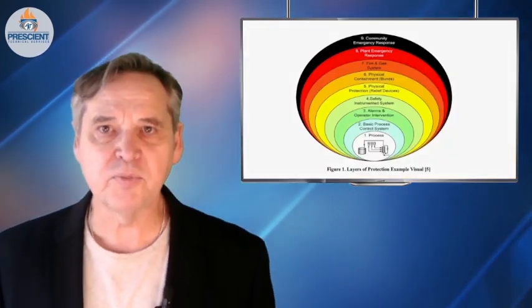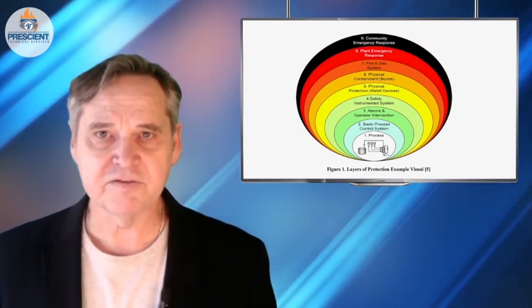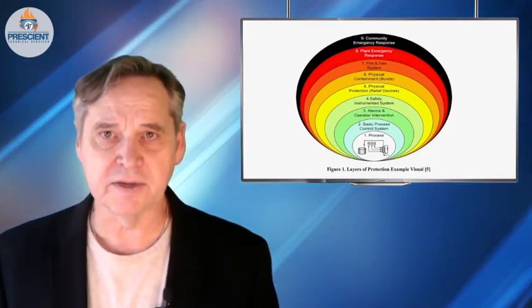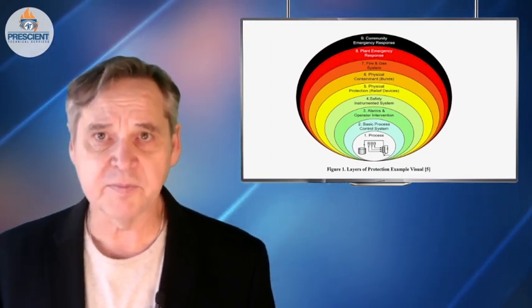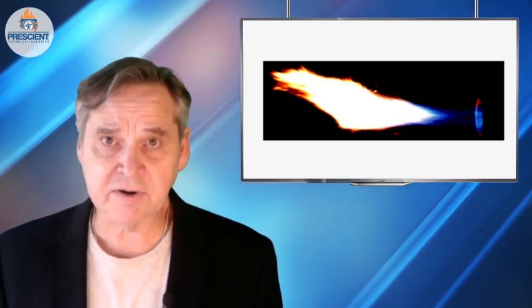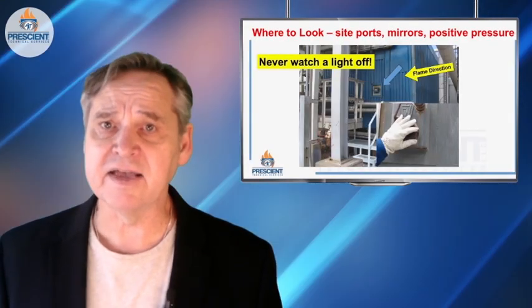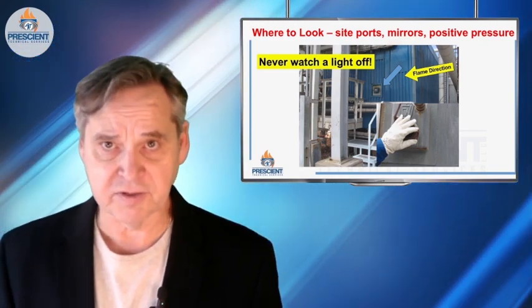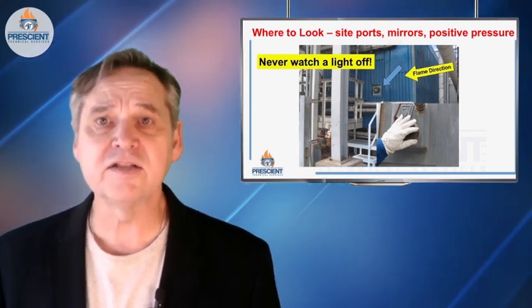How do you mitigate these risks? You do intense quality control management of the water treatment system. Some facilities use third parties to review the water treatment occurring, or build in significant redundancy. I'm also providing in the comments section a PDF of a paper on doing LOPA — layer of protection analysis — on water treatment systems for boilers. Don't forget that burners not set up properly with flames impinging on tubes can also cause premature tube failure. You need a daily flame observation program with people trained to recognize impingement, understand when it's bad, and know when things should be shut down immediately. You need to log this information.